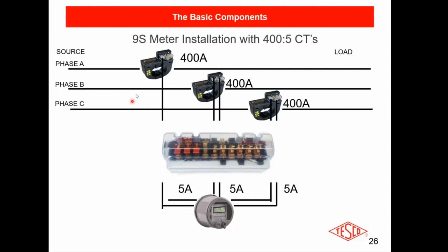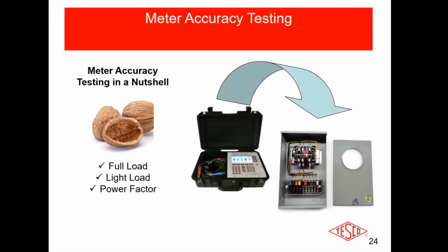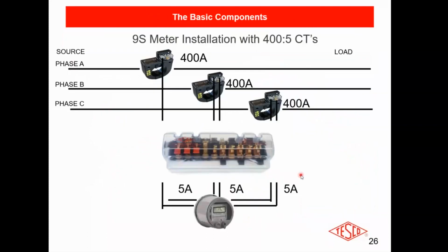So you typically have your 3 transformers on phase A, phase B, phase C. They are connected through a test switch to your meter. Okay, so if you look up here, you've got your test switch and you've got your socket. Sometimes if you put the CTs in the same cabinet, that's called a trans socket. More typically, the CTs are in a separate cabinet, usually fairly close. You want them ideally as close as possible to the meter and the test switch cabinet. Also, if you look, you see this little white dot up here? That gives you your orientation. So you make sure that these CTs are all oriented in the same direction. All right, we'll talk a little bit more about what happens if you didn't do that.